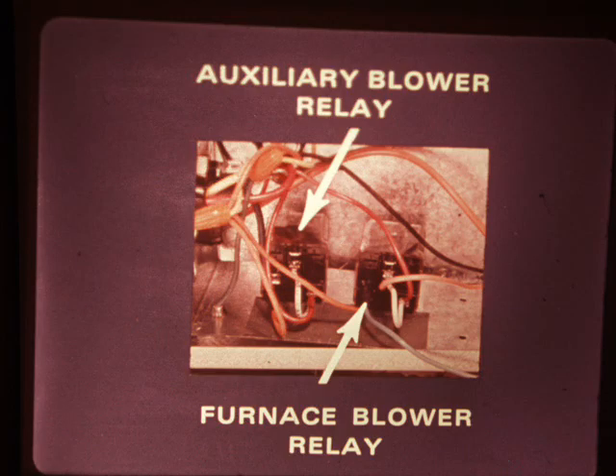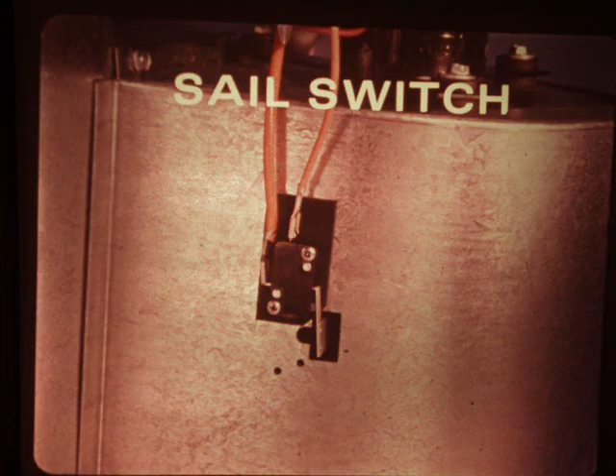There are two relays on the furnace, one for the furnace blower, the other for the auxiliary blower. When the thermostat contacts close, calling for heat, both relays are energized immediately. A sail switch in the bottom of the blower assembly responds to the flow of air generated by the blower. When the switch closes in response to airflow, the solenoid valve opens, gas flows to the burners, and ignition occurs. If for any reason the airflow is not sufficient, the switch won't close.